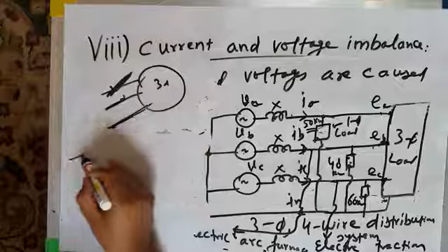Another reason is that for power factor improvement, if this is your three-phase supply and this is your three-phase load, what you do is connect a capacitor bank, a shunt connected capacitor bank, across the load. So it supplies the reactive power Q demanded by the load, and it maintains the load voltage constant. But what sometimes happens is that capacitor banks have fuses. This is a fuse, this is a fuse. Let us suppose the fuse of this capacitor blows. As soon as this fuse blows, this capacitor gets disconnected. So what will happen to the voltage of this phase? Its voltage will dip because it will not receive any reactive power. Supplying reactive power improves the voltage, but since this phase is not receiving any reactive power from this capacitor because of the blowing of the fuse, its voltage will dip and the voltage of these two is high while this one has decreased, so that results in voltage unbalance.